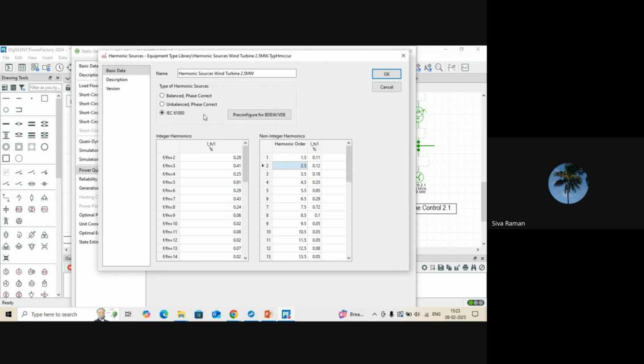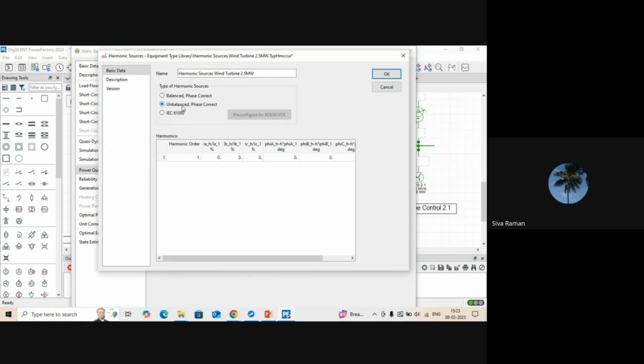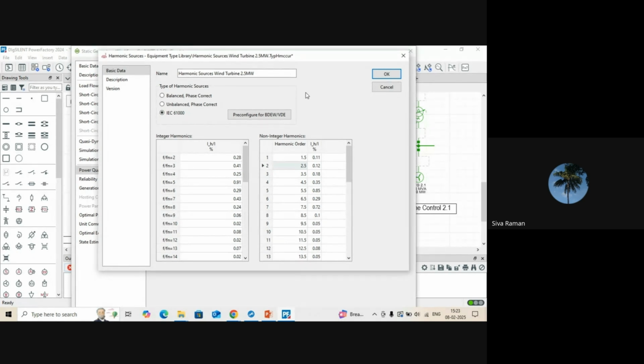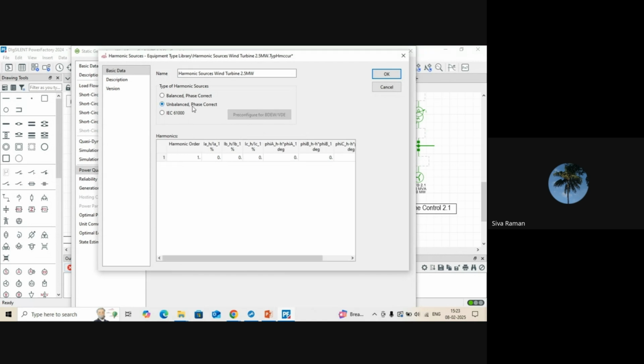And there are some situations where we have to model the balanced method, or the unbalanced method, or the IEC method. That depends on how much data we have and how much accuracy we want in the model. The unbalanced method is the more accurate method, because for all three phases we have to include the current harmonic value as well as the phase angle. This one we have to model here. Particularly, how much the voltage is and at what angle it is oscillating, that we have to model here.